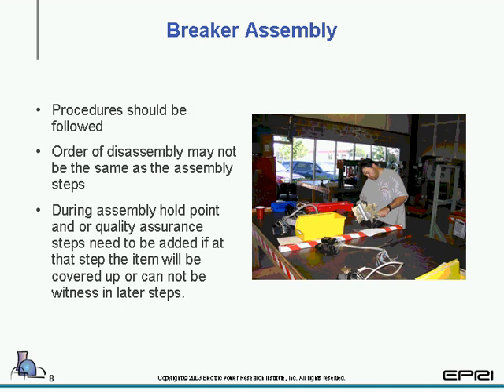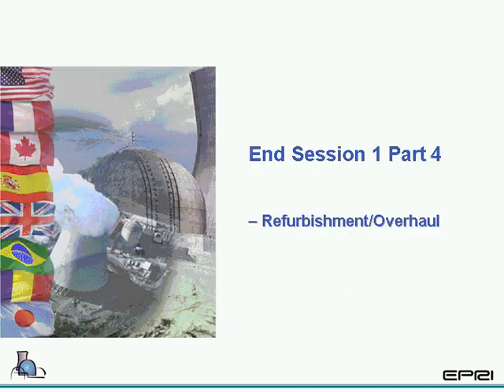The reason why it may not go back together, correct me if I'm wrong, this is more of a question to you, is I think the point you're trying to make is that the breaker may not have been assembled correctly in the first place. Is that what you're saying? Yes, you can come across it. Just because you find it that way doesn't necessarily mean it goes back that way. Sometimes it's much easier to take something apart than put it together. So when you assemble a subassembly and install it into a breaker or another large assembly, you want to make sure somebody else looks at it.